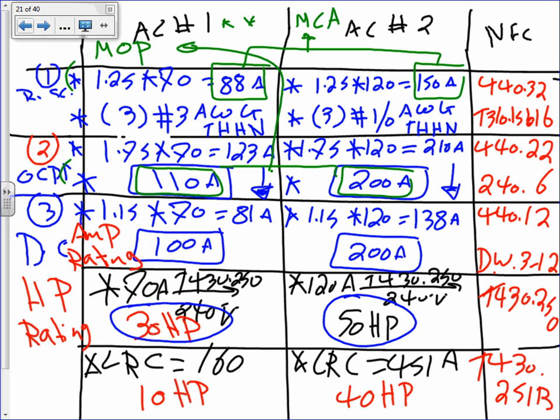So when you size the disconnect for a motor, do you normally put down the horsepower? Yes. The nice thing about the motor is, what's the horsepower rating of a 50 horsepower motor? You're given it, but when you state it, yes. When you order your disconnects, you say a 200 amp disconnect with 50 horsepower rating. You have to specify the horsepower. That will give you the disconnect size, and of course the voltage and the horsepower also give you the NEMA size, the NEMA controller size.